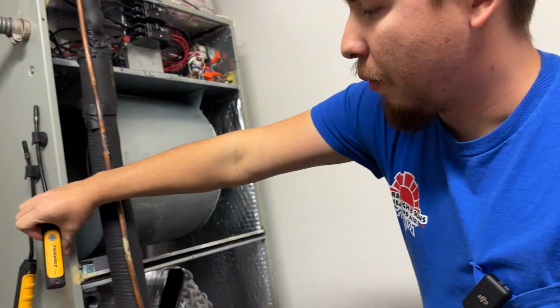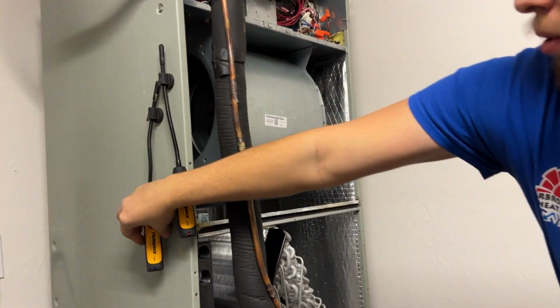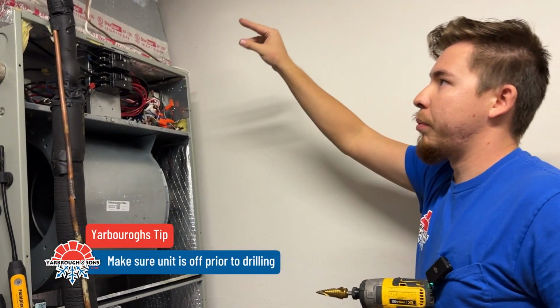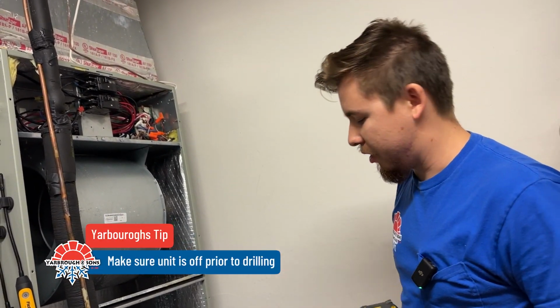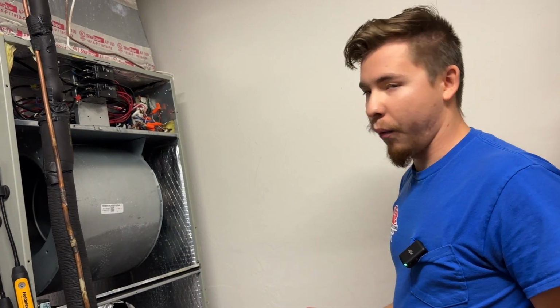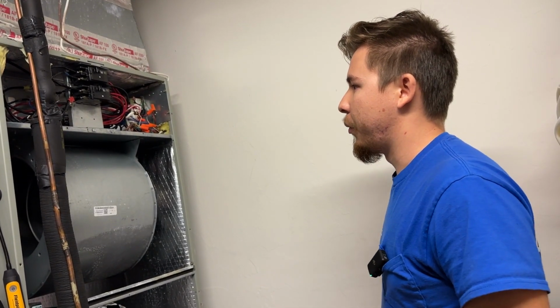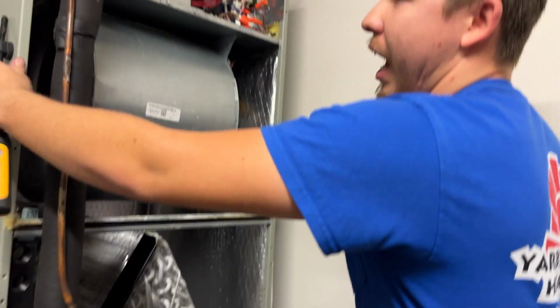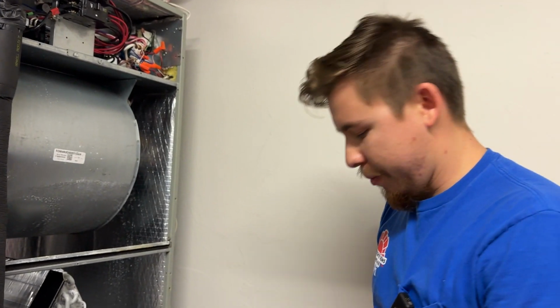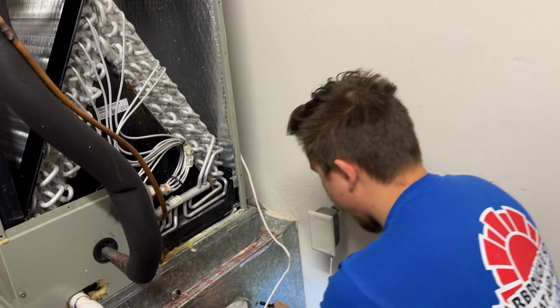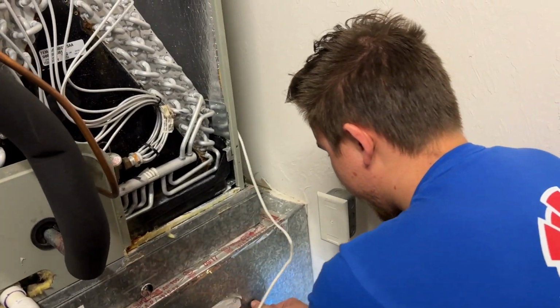And now what I'm going to do is get my temperature probes here. I've got one for your return and one for your supply. I'm going to drill a hole into the ductwork to put them in, not causing any harm to the system, just so I can get a more accurate wet bulb, temperature, and see what I should be reading. That's your temperature probe right there. I'll be able to read it on my Fieldpiece app here soon. After we get done working on it, we're going to tape it up so it doesn't push any airflow out or suck any outside air in.